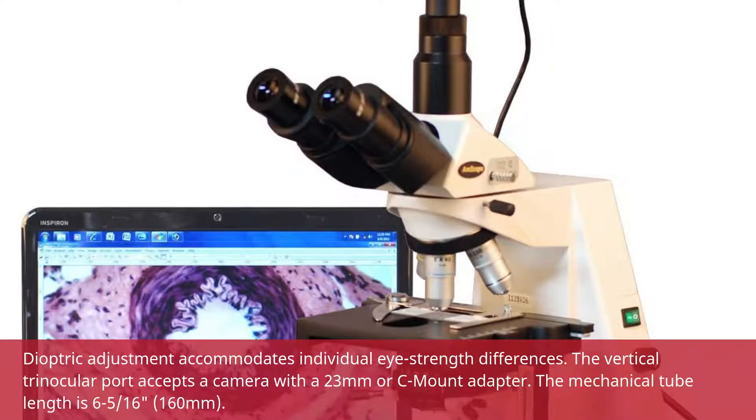Dioptric adjustment accommodates individual eye-strength differences. The vertical trinocular port accepts a camera with a 23mm or C-Mount adapter. The mechanical tube length is 6 and 5/16ths inches, or 160mm.